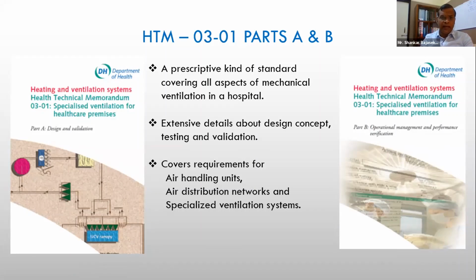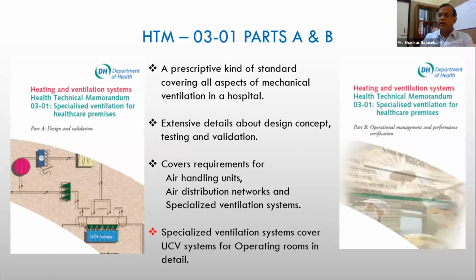It covers the entire air distribution network. The ASHRAE document does not cover it. The ASHRAE standard 170 does not cover air handling units. And HTM 03-01 specifically covers specialized ventilation systems which are used in operating rooms and ICUs.